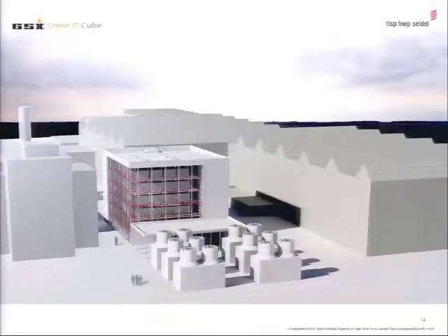The special part of this concept is that we will use waterfalls for cooling. So it's completely passive cooling. It's the only way you can achieve a PUE value of something about 1.06. You never achieve such a power utilization efficiency with active cooling. So this is not just science fiction. We already have at GSI a working prototype, which I will show soon. We reached the design value of the PUE, and we survived even the hottest summers with this cooling.